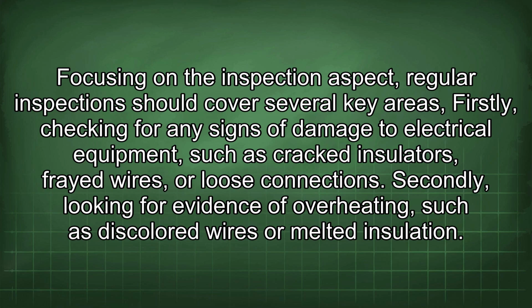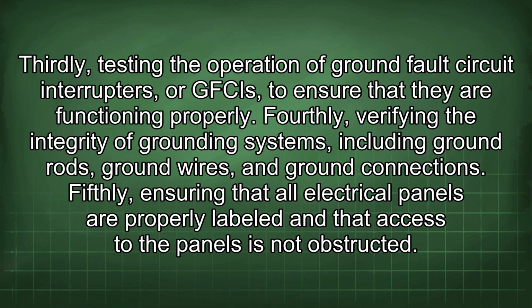Firstly, checking for any signs of damage to electrical equipment, such as cracked insulators, frayed wires, or loose connections. Secondly, looking for evidence of overheating, such as discolored wires or melted insulation. Thirdly, testing the operation of ground fault circuit interrupters, or GFCIs, to ensure that they are functioning properly. Fourthly, verifying the integrity of grounding systems, including ground rods, ground wires, and ground connections. Fifthly, ensuring that all electrical panels are properly labeled and that access to the panels is not obstructed.